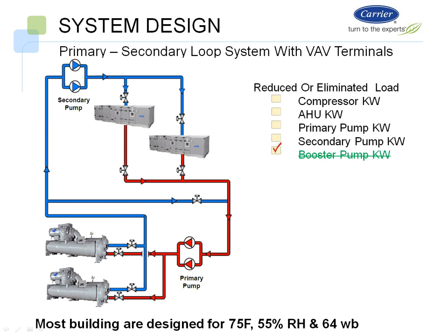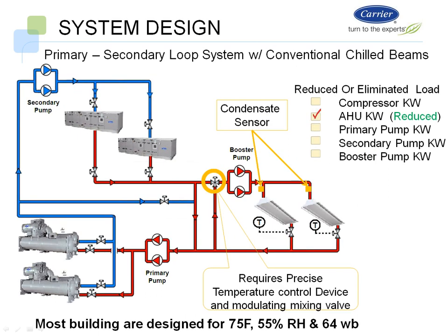At least they have to provide 55-degree air to VAV boxes, and then typically your VAV boxes on the perimeters are going to be fan powered of some sort, either series or parallel type boxes. So then you have that horsepower that you have to consider if it's series, where the fan in each individual VAV box will be running all the time, and on the parallel type box when you're in heating configuration as first stage heat.